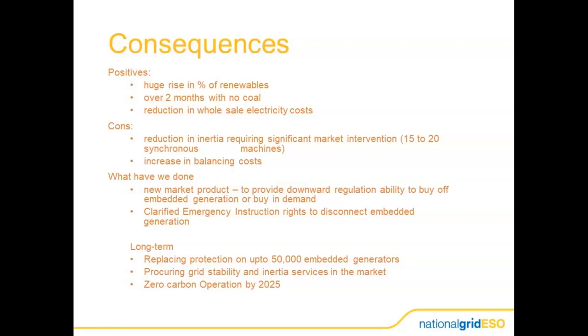However, as a system operator, there's some not so good things as well. Obviously a huge reduction in inertia on the system, so we're having to buy, in the worst situations, sort of 15 to 20 synchronous machines in the market. But in order to create the headroom to get those machines on, we're having to constrain off interconnectors and renewables in order to create the space to bring on those 15 to 20 synchronous machines at minimum stable generation to provide the inertia.